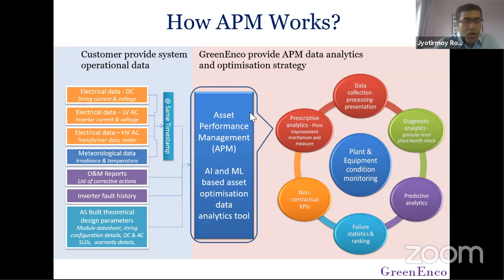We take the DC side string-level voltage and current, or the LV AC side and HV AC side, including meteorological data—irradiance and temperature. All four sets of data should be at the same timestamps, whether 5, 10, or 15 minutes. Ideally, if the data set period is one year, a seasonal impact can be seen, but even if a plant has less than one year of data, it can still work.